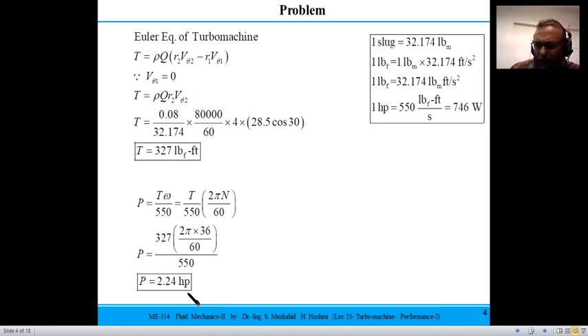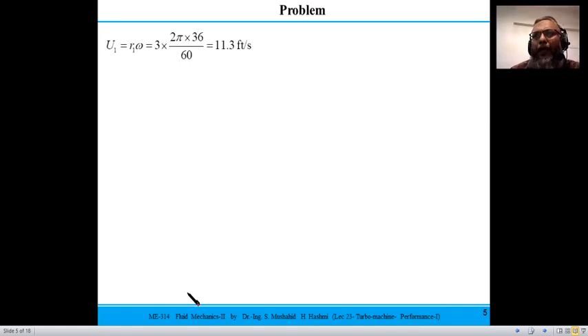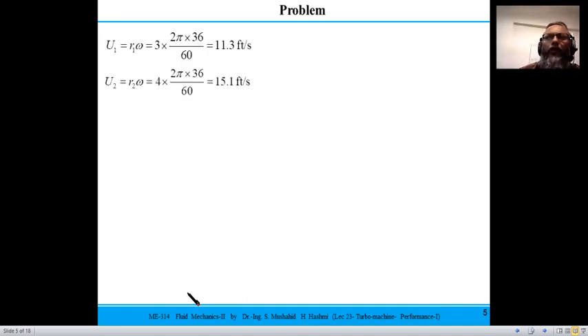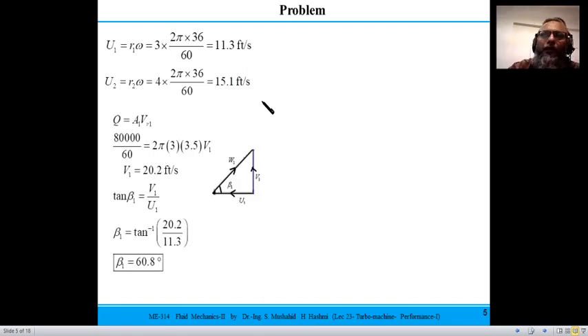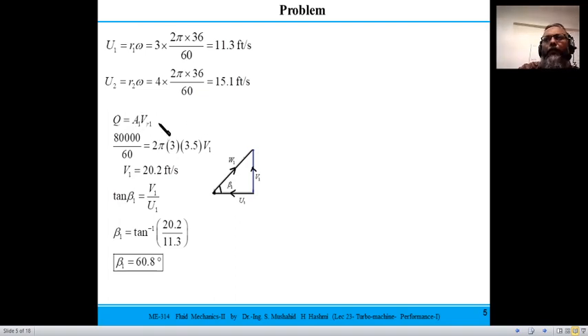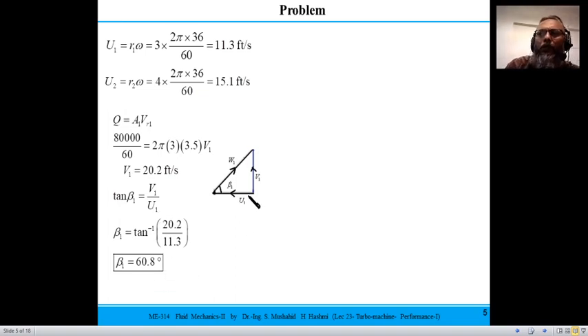To find blade angles, first calculate blade velocities: u1 = r1 · ω and u2 = r2 · ω. Since r2 > r1, the blade velocity at the outlet is larger. The radial velocity v1 = vr1 is found from the volume flow rate divided by the inlet area, since v_θ1 = 0. From the inlet velocity triangle, tan(β1) = v1 / u1, and solving gives β1 = 60.8 degrees.